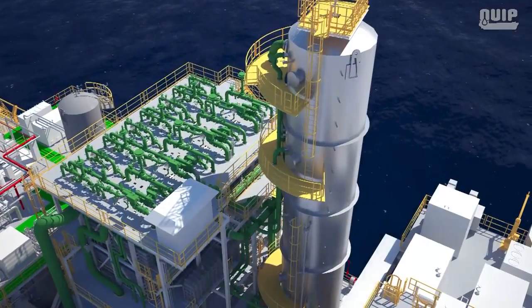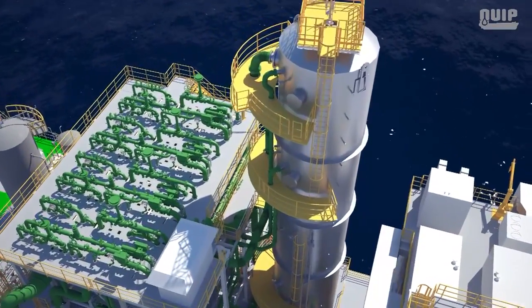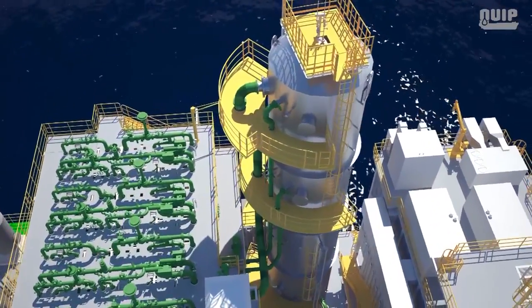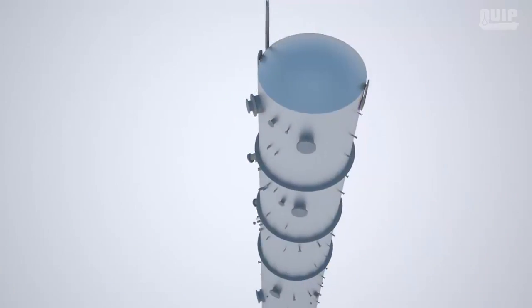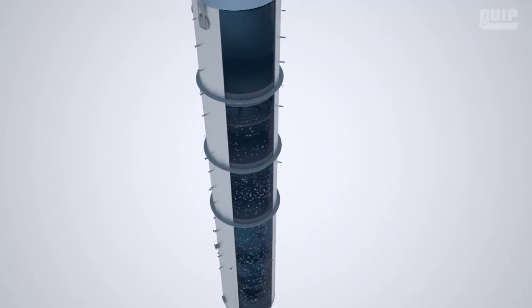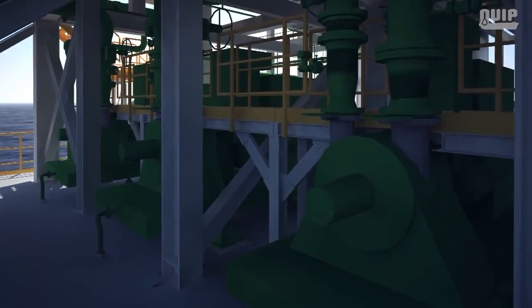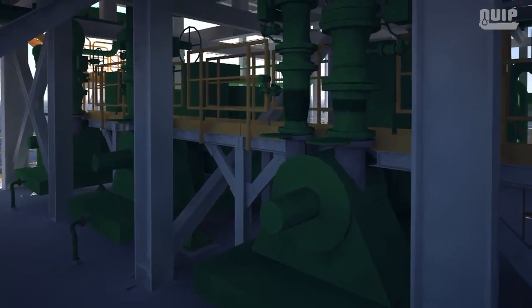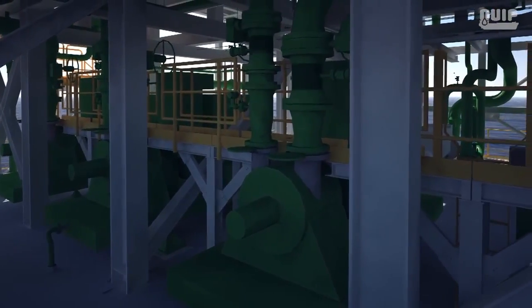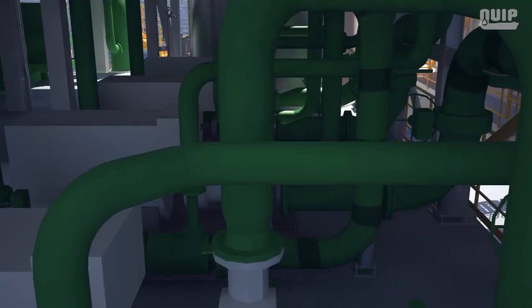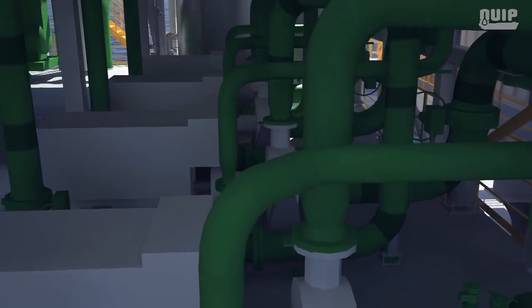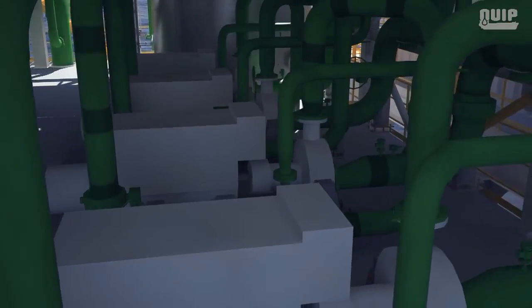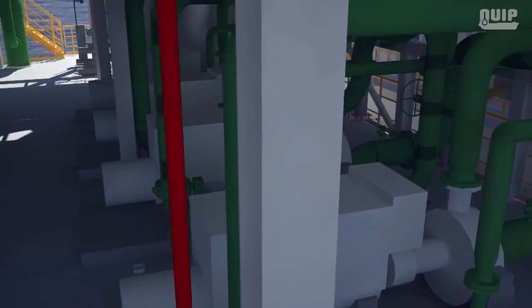The low sulfate water is sent to the de-aeration tower, which reduces the amount of oxygen in the water. The treated water is sent for processing through booster pumps, which elevate the pressure to 9 bar gauge. After processing, the treated water goes to the injection pumps. The purpose of the injection is to pressurize the reservoir, attenuating the loss of energy caused by petroleum production.